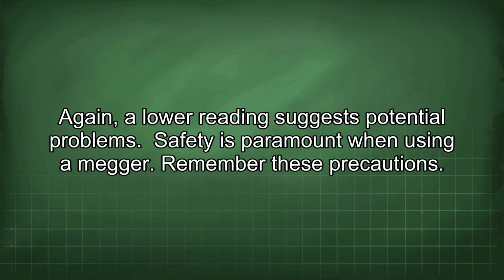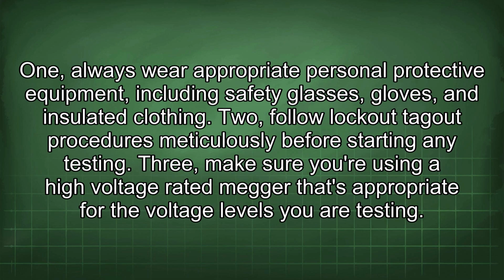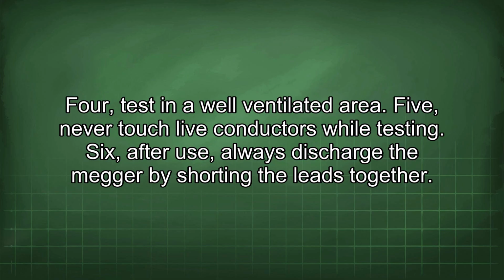Remember these precautions. 1. Always wear appropriate personal protective equipment, including safety glasses, gloves, and insulated clothing. 2. Follow lockout-tagout procedures meticulously before starting any testing. 3. Make sure you're using a high voltage rated Megger that's appropriate for the voltage levels you are testing. 4. Test in a well-ventilated area. 5. Never touch live conductors while testing. 6. After use, always discharge the Megger by shorting the leads together.